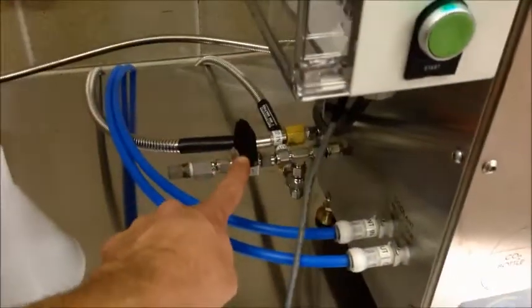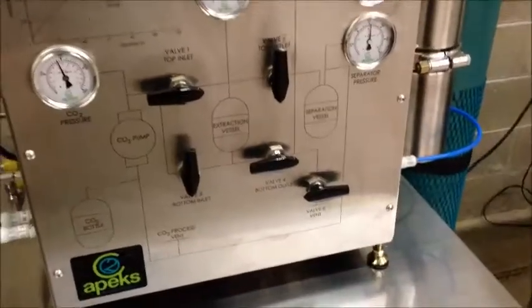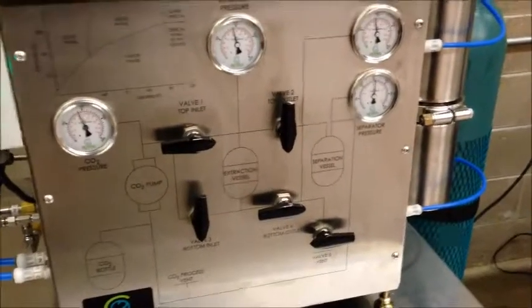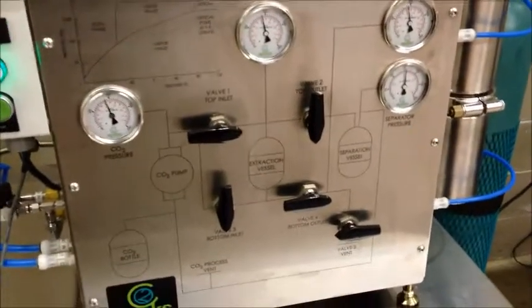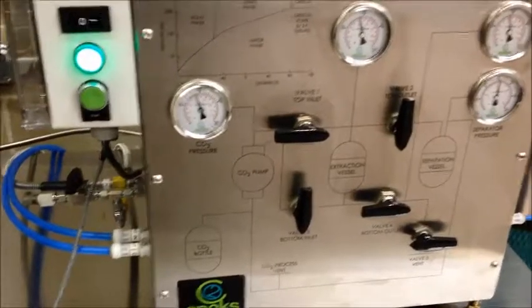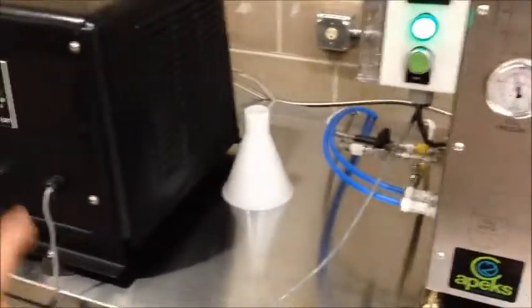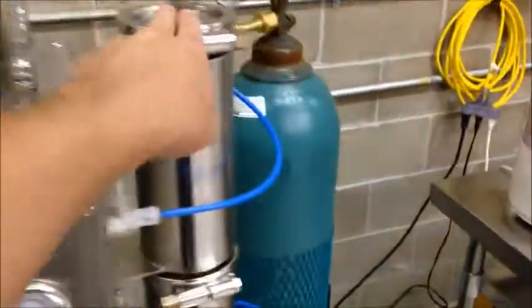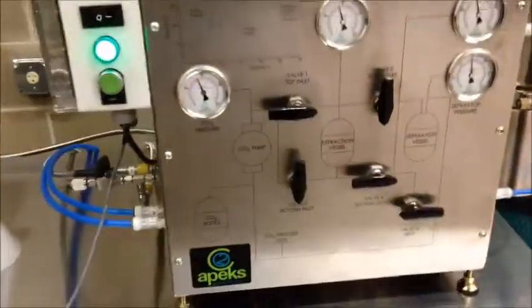So if you open this one here, so if you get down to about 205, 210 psi, and it's not wanting to recover that last 5 psi, and you want to end the recovery, just crack this valve open. It'll drop the pressure below 200. The pump will shut off, and then you're good to go ahead and close your CO2 bottle. Open up this valve, and that releases all the pressure. Then you're safe to get in here and here.